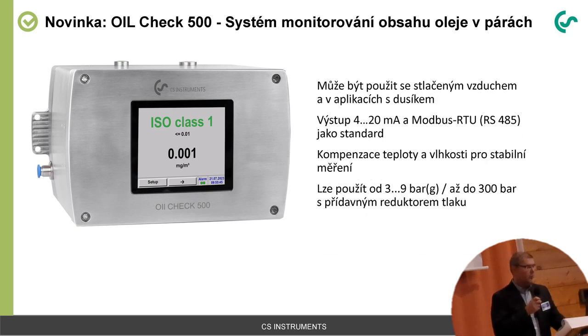Further on, it could not only be used in compressed air, it could also be used, for example, in nitrogen. It has a 4 to 20 milliamp output and a Modbus output as a standard. It has temperature compensation and humidity compensation to have stable measurements, and it could be used in normal compressed air, let's say from 3 to 9 bar, but we also have a version which could be used up to 300 bar.